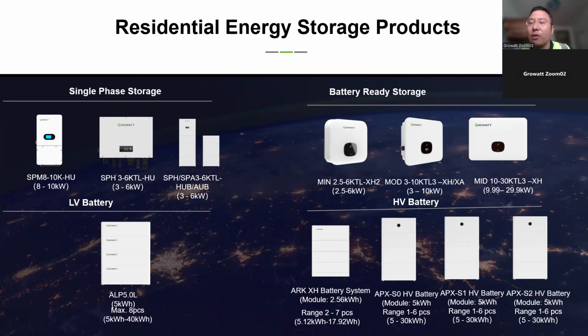All the installer had to do is use the CT at the main switch, that's it. I expect the installer can finish the all-in-one installation in less than 1 hour. We built in a smart meter, we built in the ATS, and also we built in the DC isolators between inverter cables and batteries.